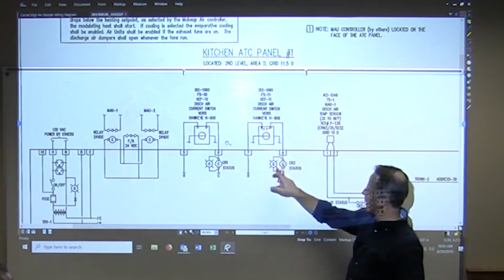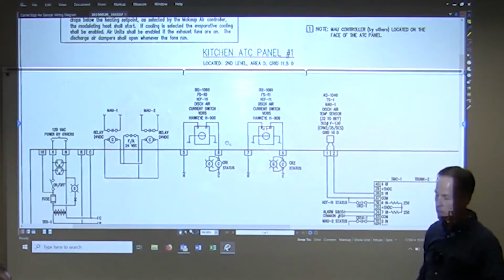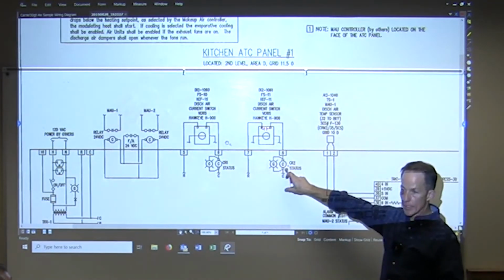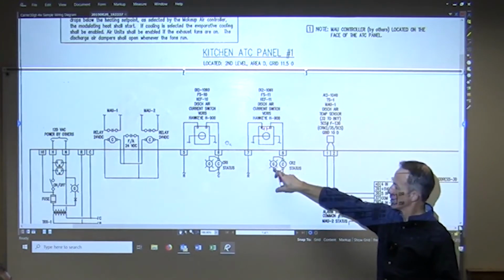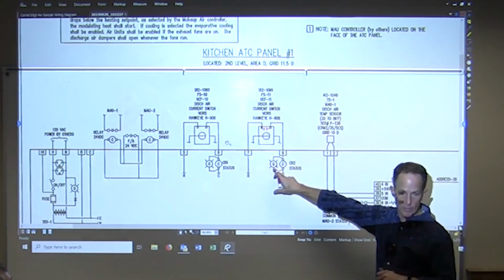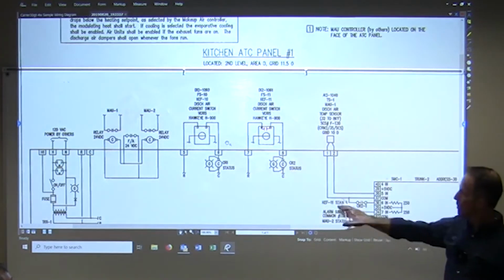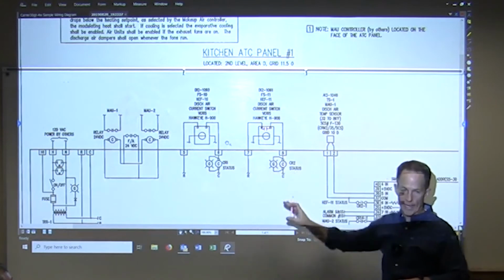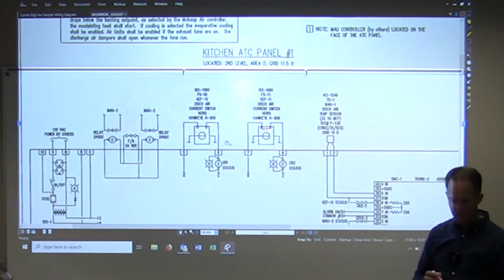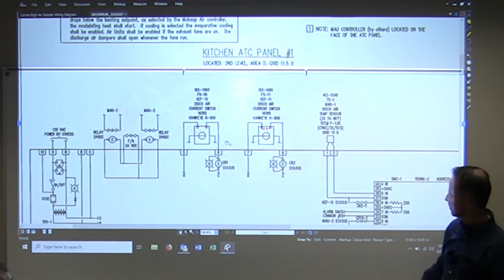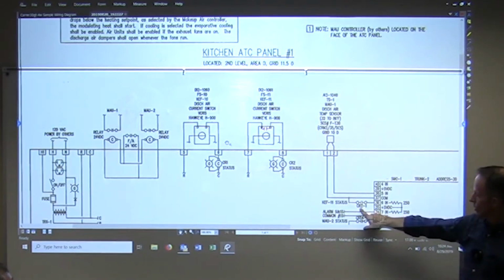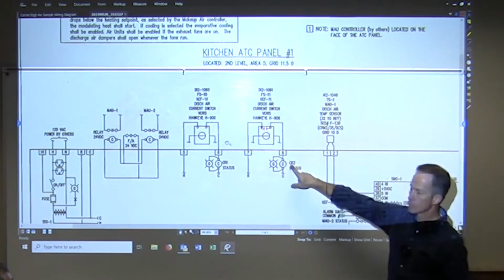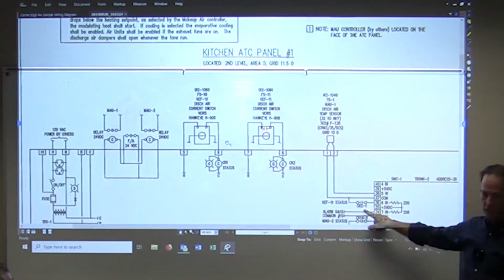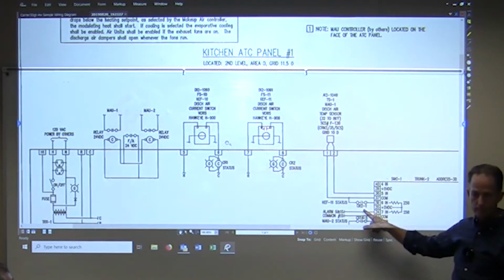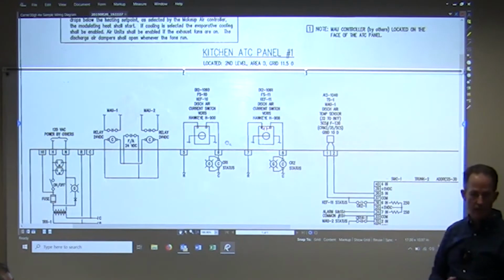If this closes, what happens here? Energizes that coil. Green light. That relay coil gets energized. Green light turns on maybe in the panel front, something like that, so we have some status. Okay. How do we know what this affects? When that relay turns on, where does it go? What does it affect? What does it change? CR2. Okay, so the CR2 here corresponds with that. The -1 tells us what? One contact. First of the contacts, first set of the contacts.